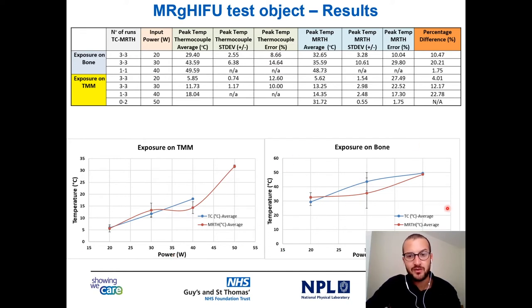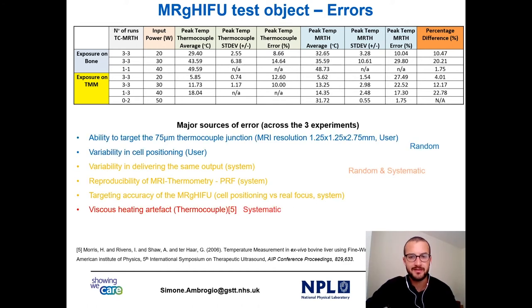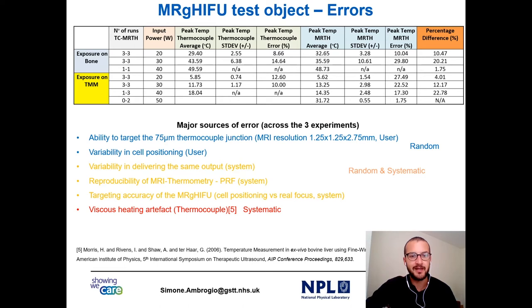These are simple plots that show the temperature rise as a function of power. Obviously, with exposure in bone the temperature is quite high, so you lose a bit of linearity in terms of temperature dependency. If you think these errors are quite big, actually they are not, because there are many sources of error across the experiment. These errors are both random and systematic. In particular, there is the ability to target the 75 micron junction of the thermocouple, and there is the viscous heating artifact. The viscous heating artifact is due to the interaction between the ultrasound fields and the thermocouple. This error has been minimized by choosing a small thermocouple of 75 micron, which is about 5% of the wavelength of the beam, and using the second derivative method, as described by Morris et al.